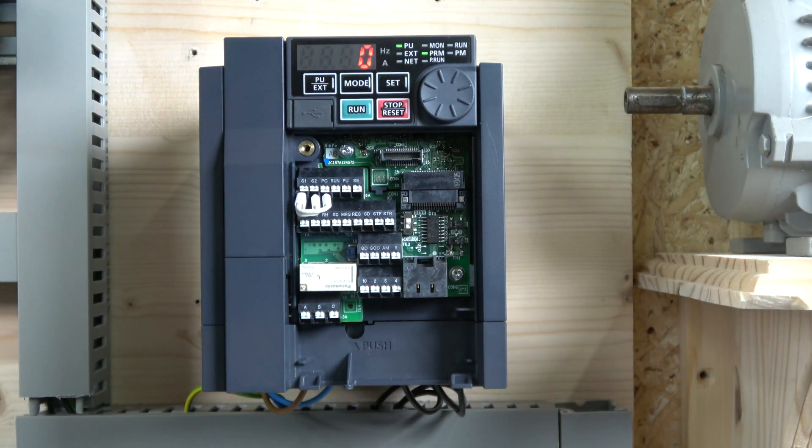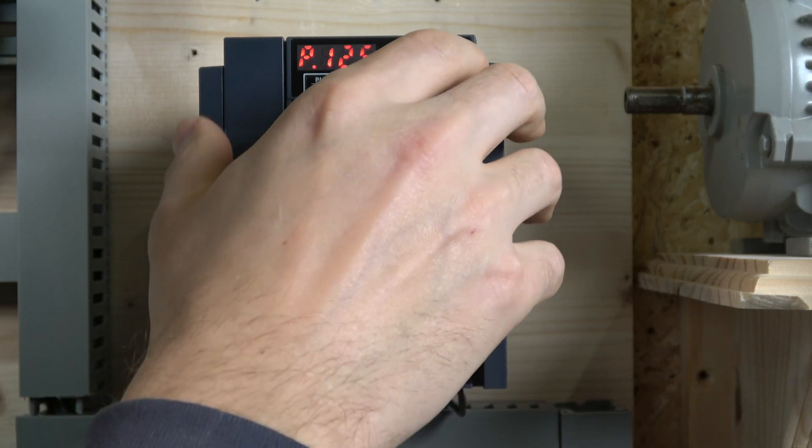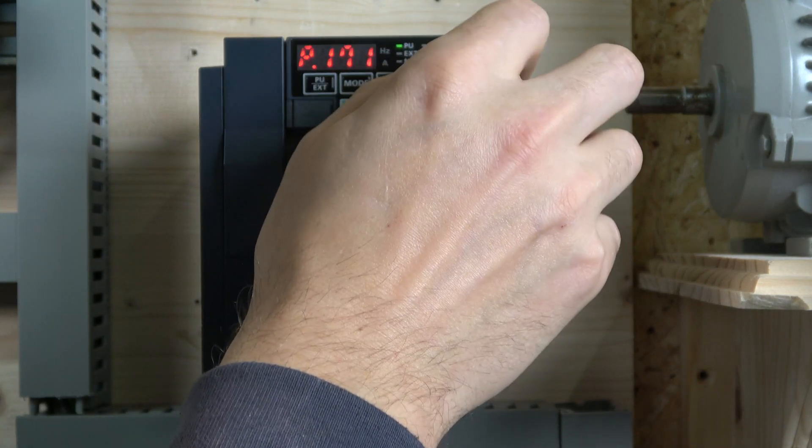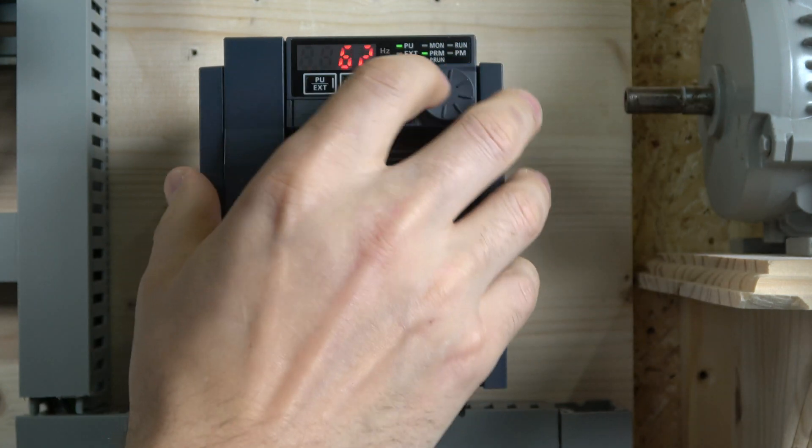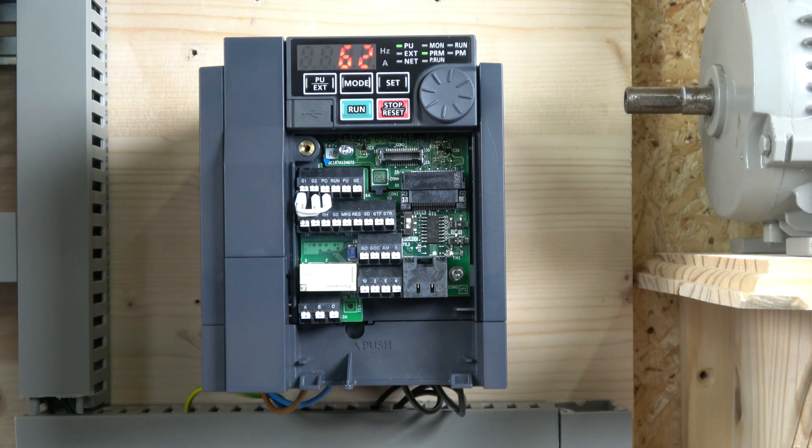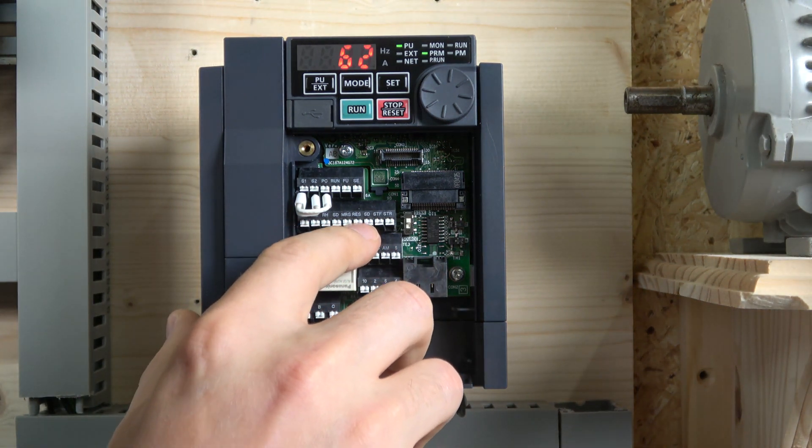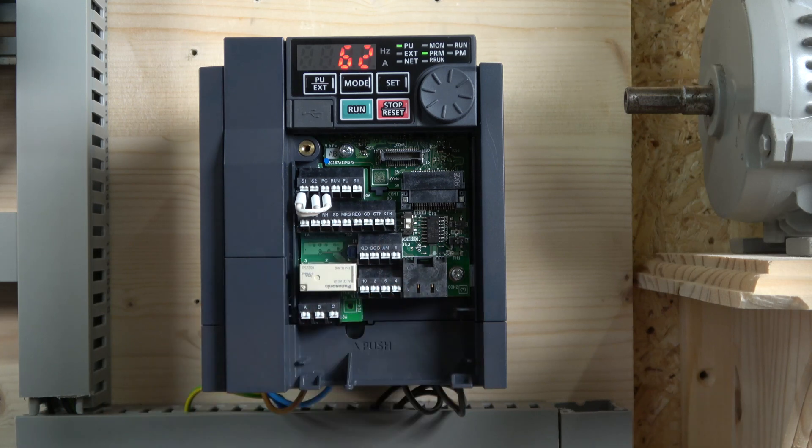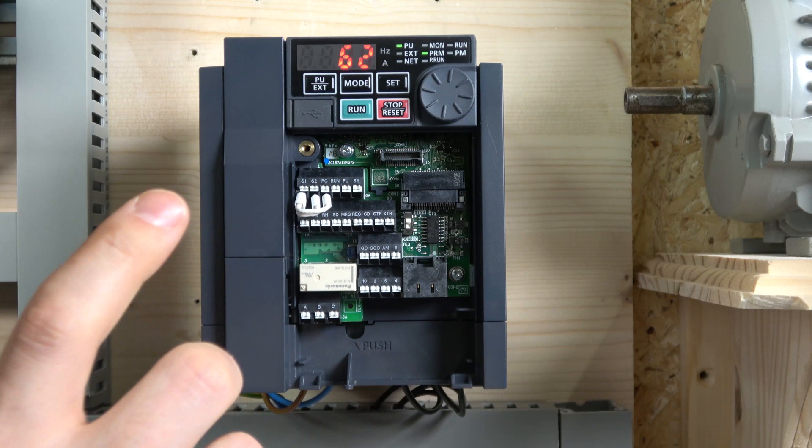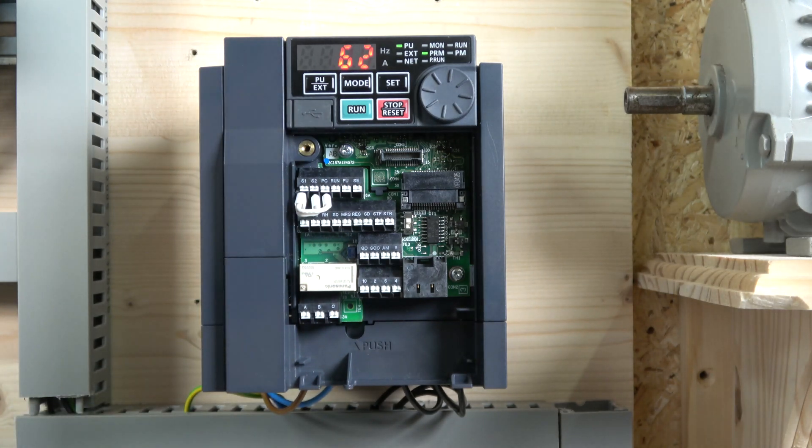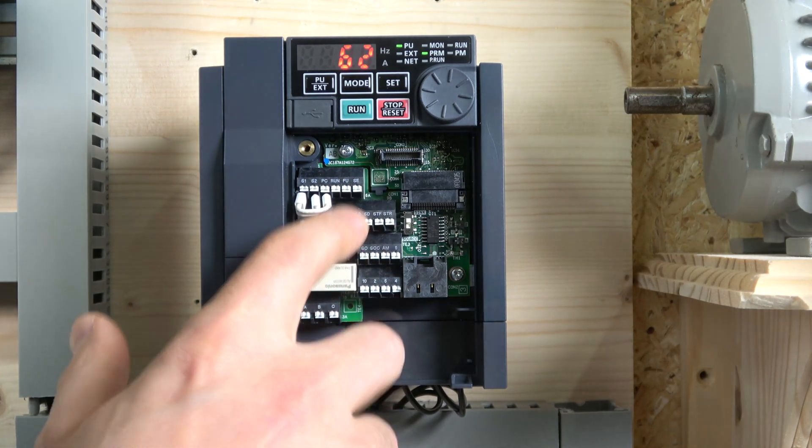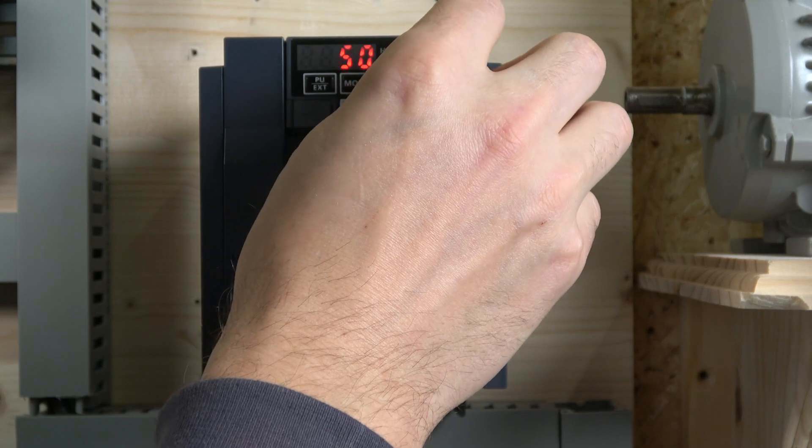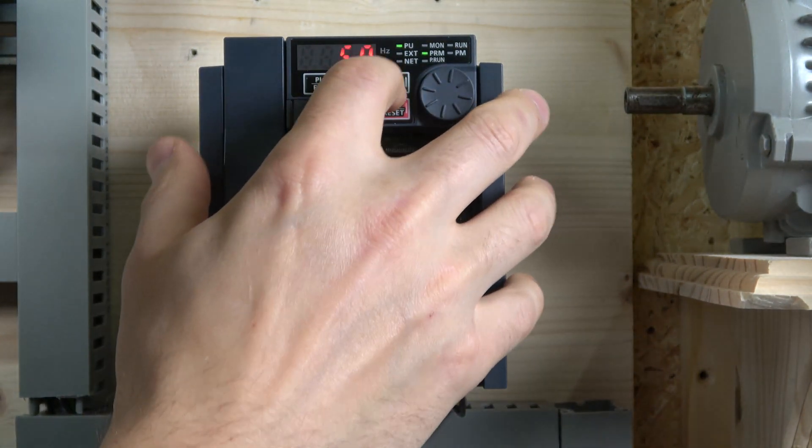Next we're looking at parameter 184. I'm going to be using RES as my start PLC run signal. That's something you definitely need. If you don't know what that is, check out the video where I talked about FR configurator and its PLC functionality. We're going to set that to 50, so that will be the number to start the PLC.